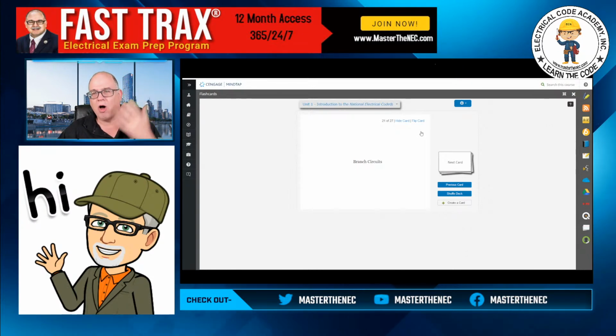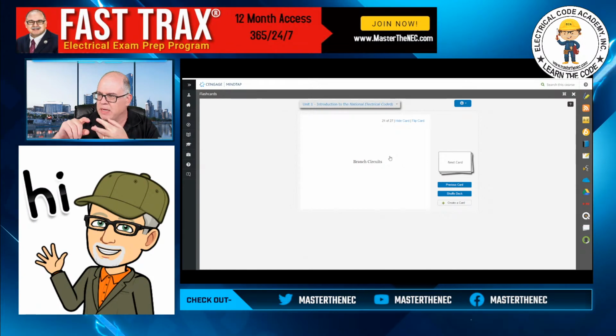All right, so I encourage you to make flashcards on all important tables like 250.122 for equipment grounding conductors. I want you to make it for 250.102(C)(1) for supply side bonding jumpers, grounding conductors, main bonding jumpers. I want you to size them for 250.66 for grounding electrode conductor sizing. Just do it and get used to doing motors. Do 430.248, 249, 250, trying to find the FLC, depending on whether it's single phase or three phase. The more you do this, the better you will become.